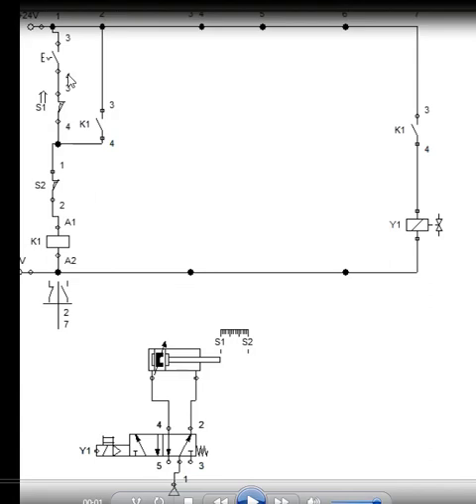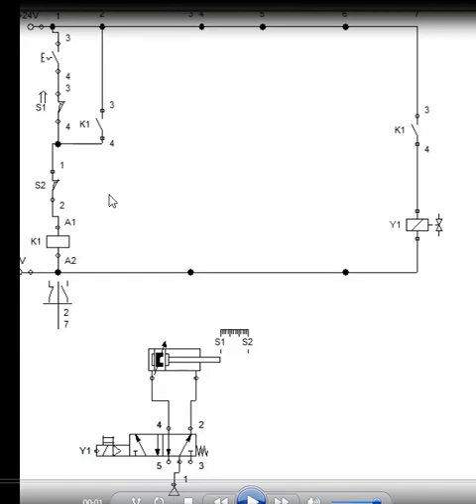So as soon as this toggle switch is pressed, the current can pass through this S1 which is closed, S2 which is closed and it will reach K1. As soon as it reaches K1, this K1 coil gets energized and this K1 coil will close this K1 contact, and the current will be supplied to Y1.